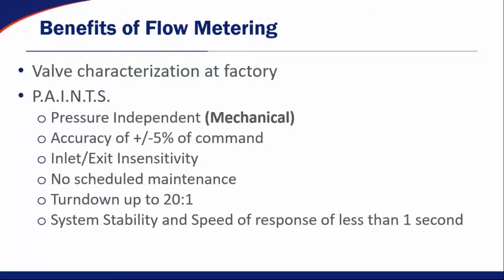measurement. And then we have this acronym called PAINTS. Pressure independent mechanically, so the valves are going to automatically adjust to the changing duct pressure without the need for a flow sensor and actuation to be able to try to maintain a fixed set point.